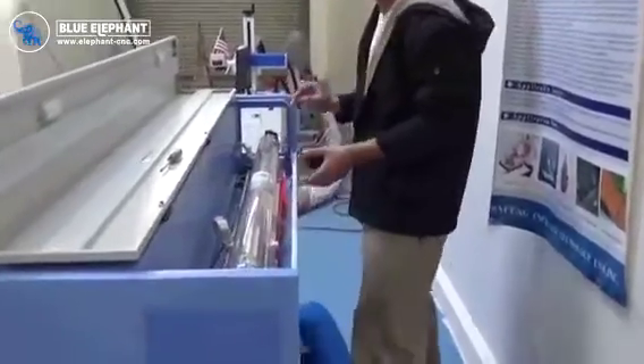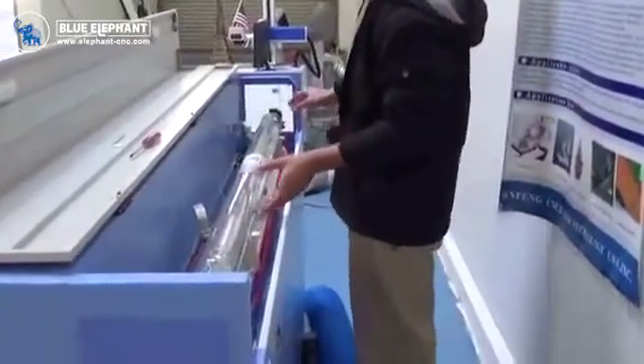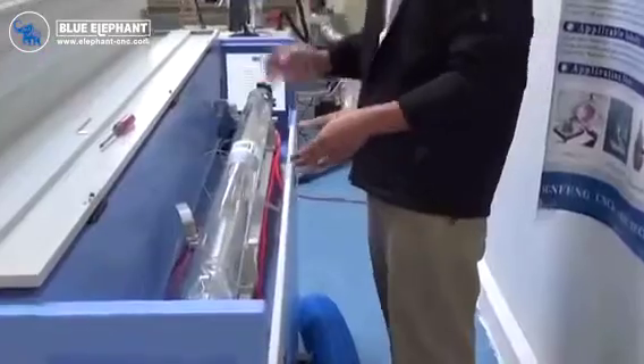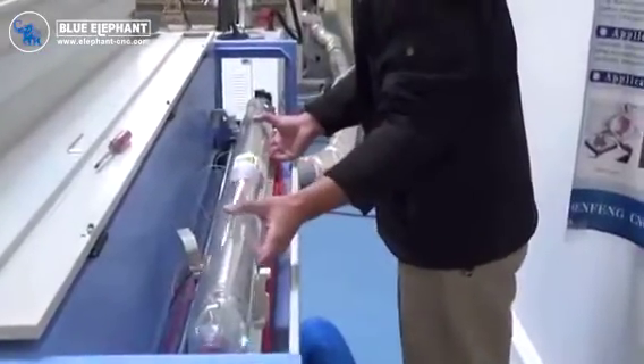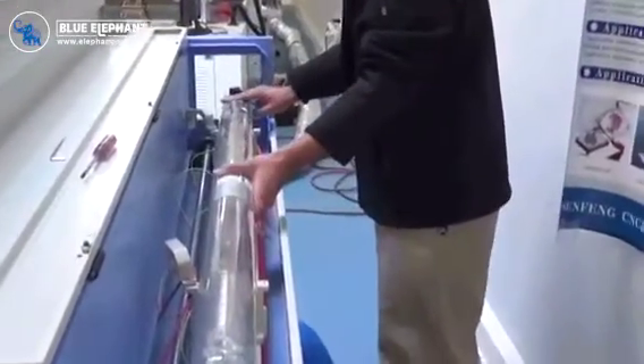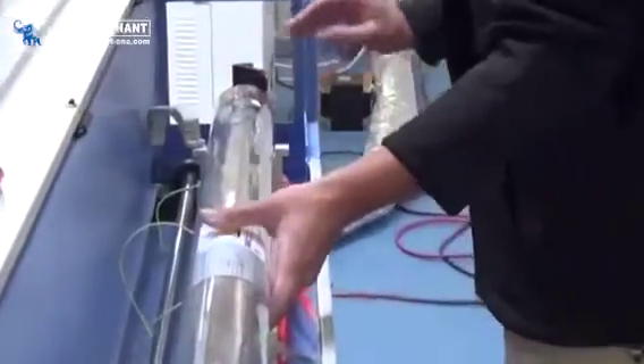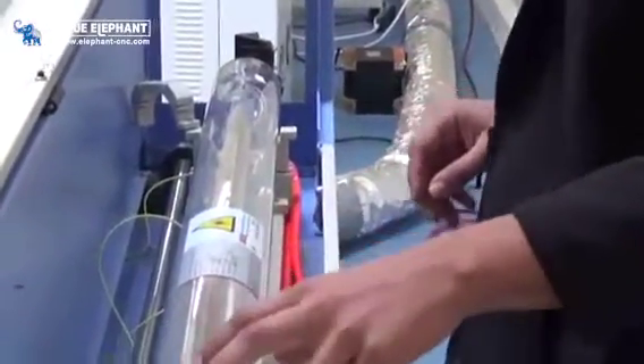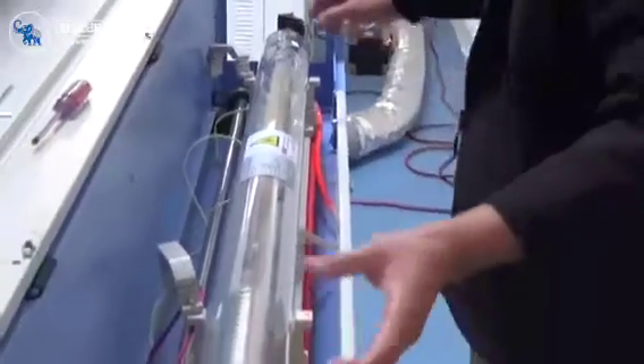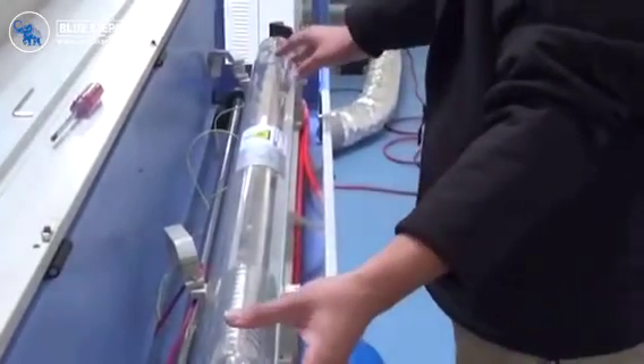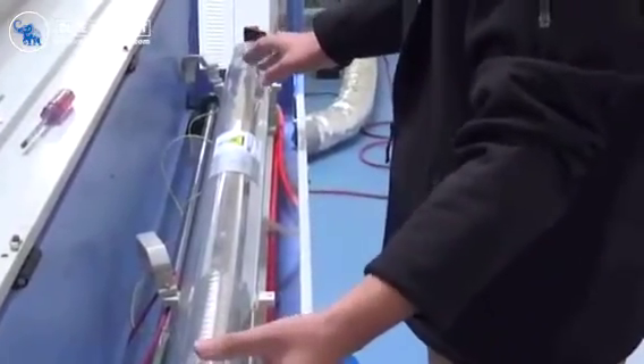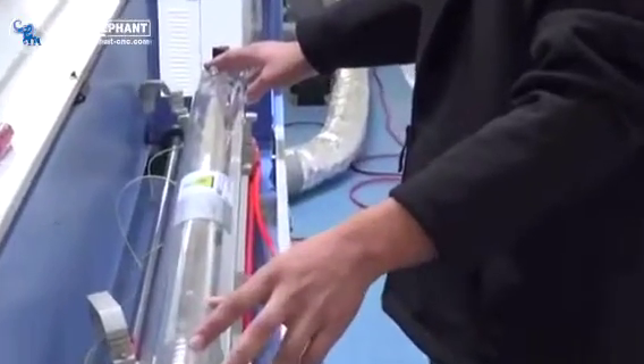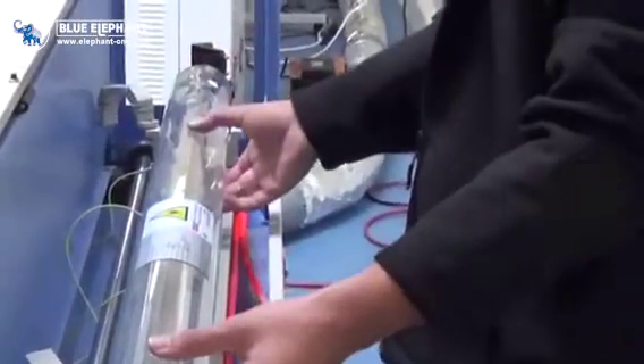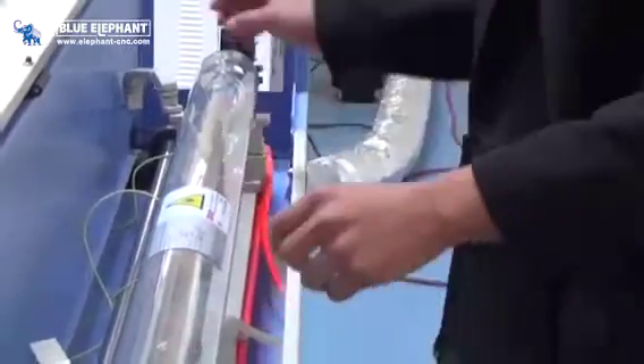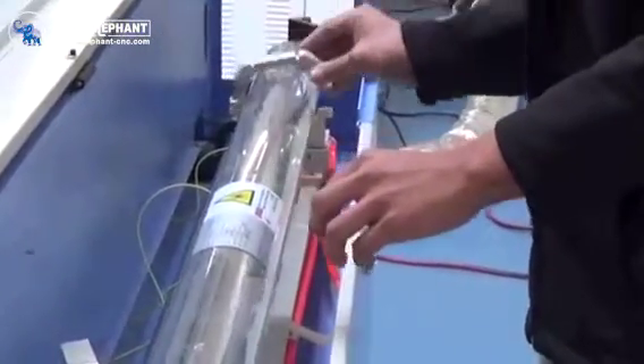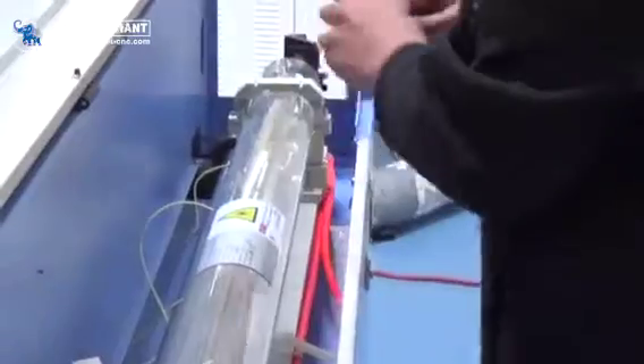We want the laser head to be approximately 2 inches away from the first reflecting mirror. You can use 3 fingers to roughly estimate that distance. Make sure the water in and water out face opposite directions - water in should be down and water out should be up. Once done, we secure the laser tube with our Allen wrench.